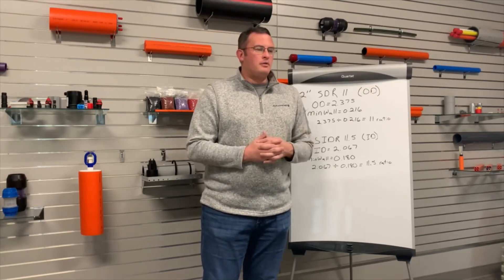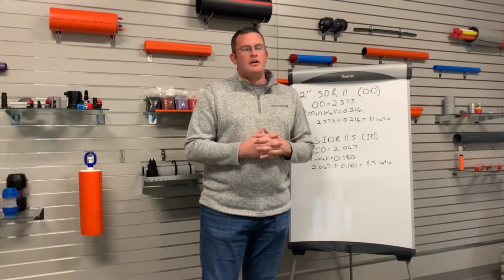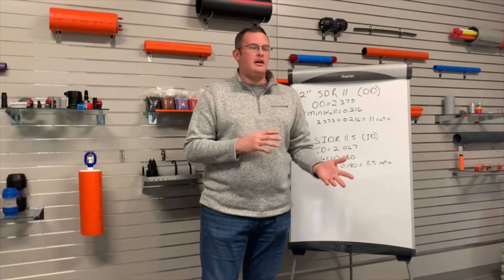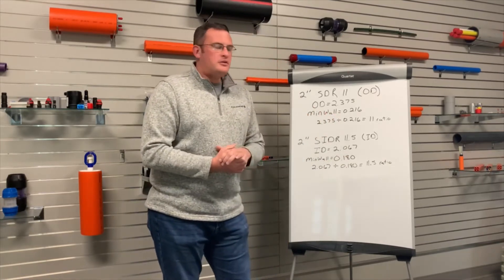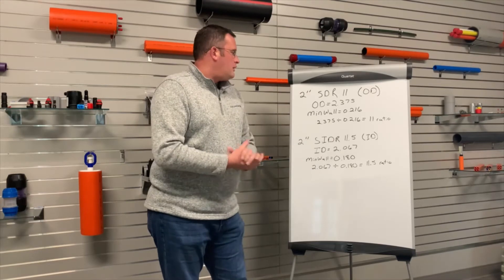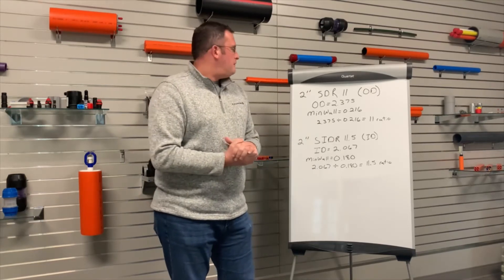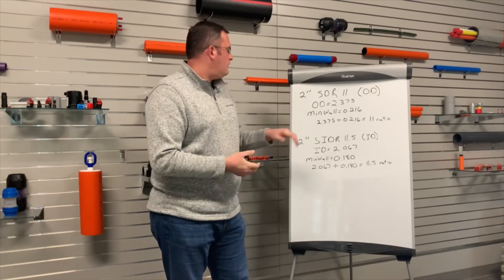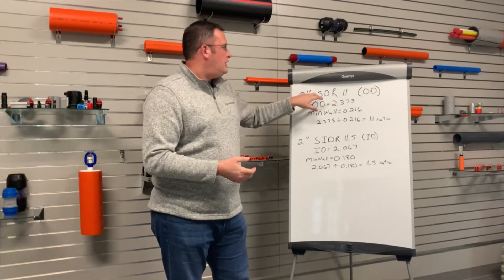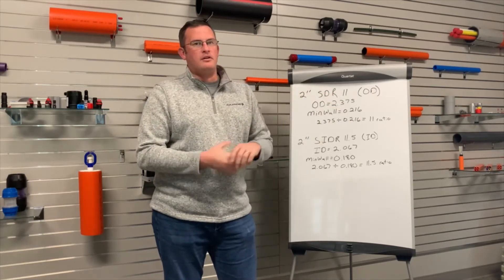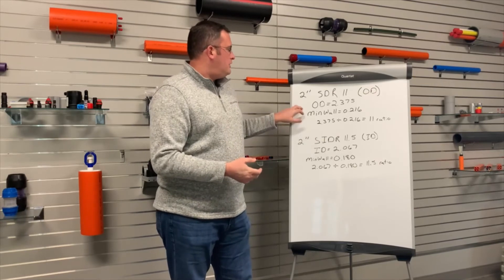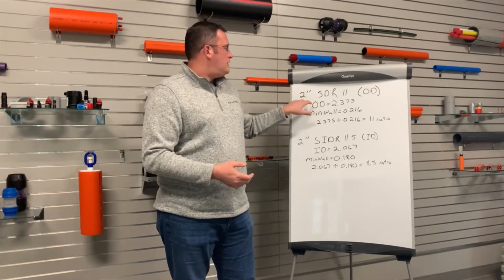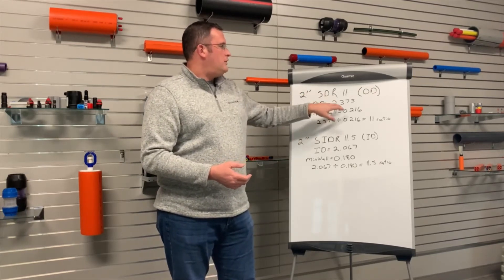The calculations and formulas for understanding the wall thicknesses and how they vary and work in relation to the ID and OD are very simple. Just for explanation purposes, I've made a couple quick calculations here to share with you guys. First is our 2-inch SDR 11. SDR is the OD-controlled wall thickness ratio. You can see that the OD of 2-inch SDR 11 is 2.375.